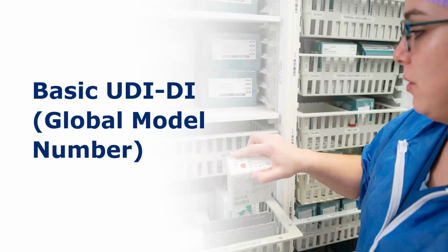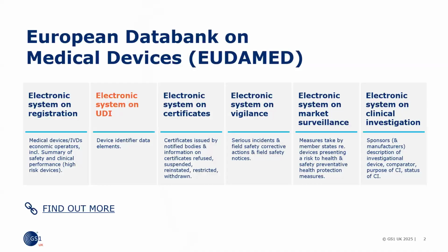This module introduces the concept of the basic UDI-DI and how it is created. This is an identifier introduced by the EU Commission as part of the UDI requirements of the EU Medical Device Regulations, and is the main key in the database and relevant documentation to connect devices with the same intended purpose, risk class, and essential design and manufacturing characteristics.